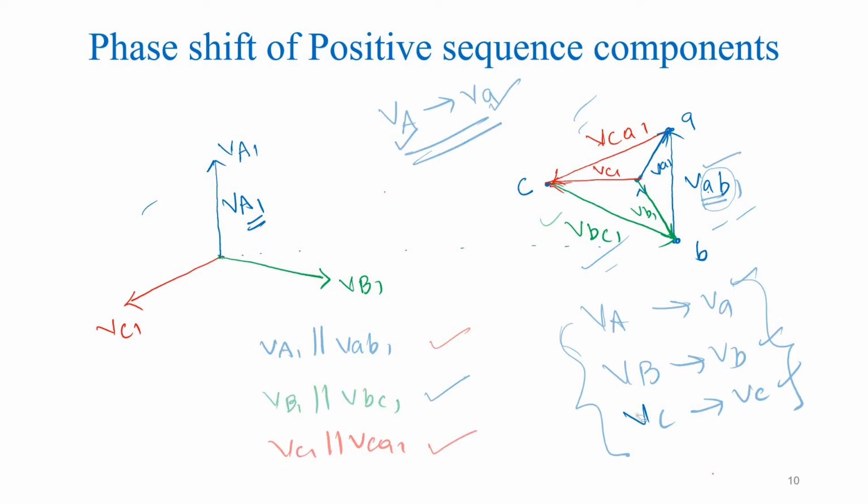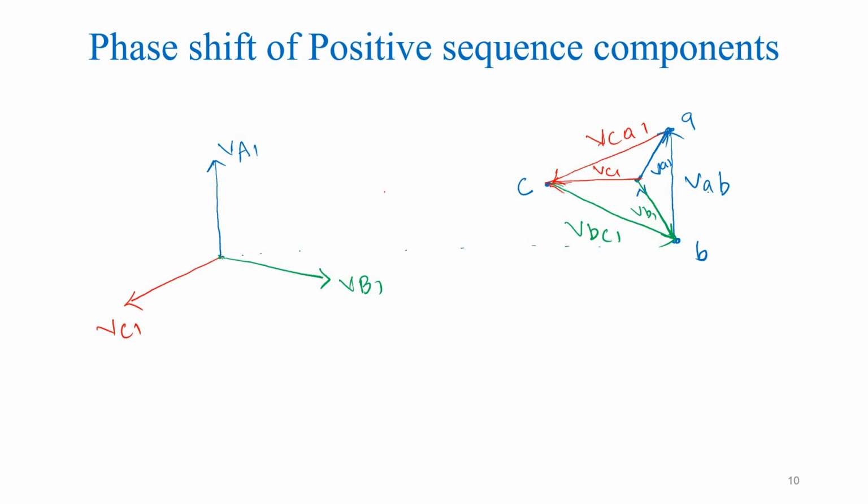That's it. Now how to check these components are having 30 degrees phase shift? So for that, let us mark the LV side phasor representations on the positive sequence diagram itself. I am going to mark the LV side quantities with the dotted lines. So the position you can observe here, in the same position I am going to mark. This is VA1, VB1 and this is VC1.